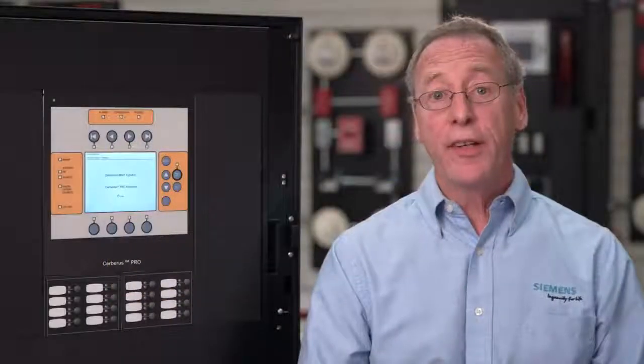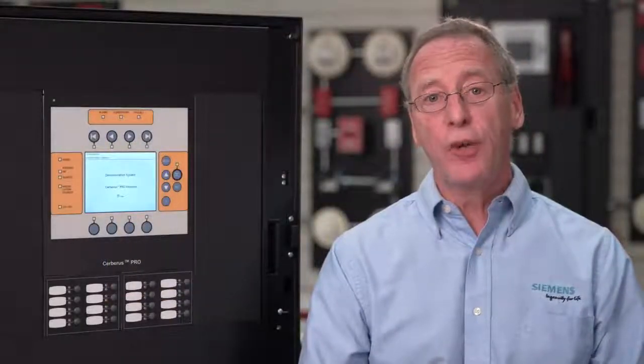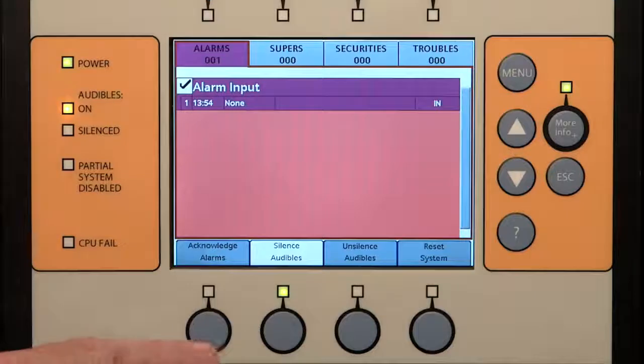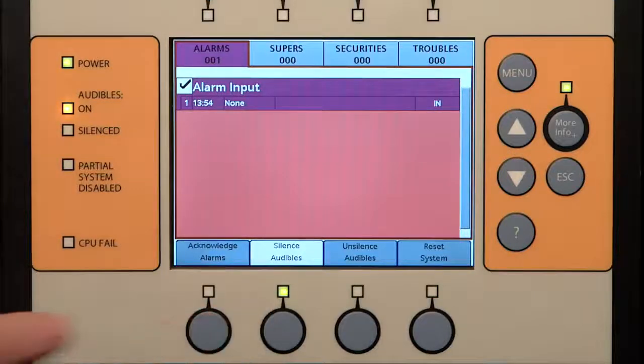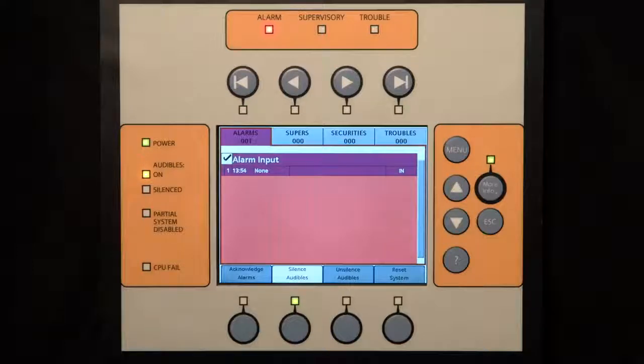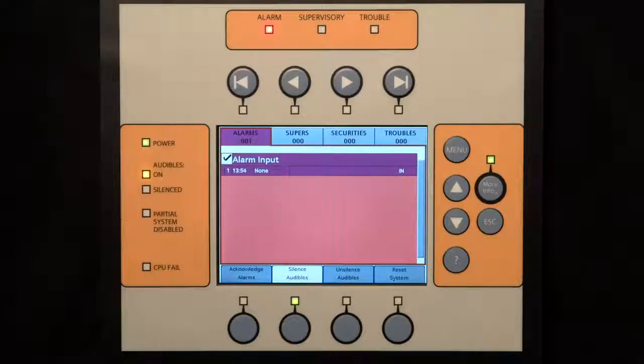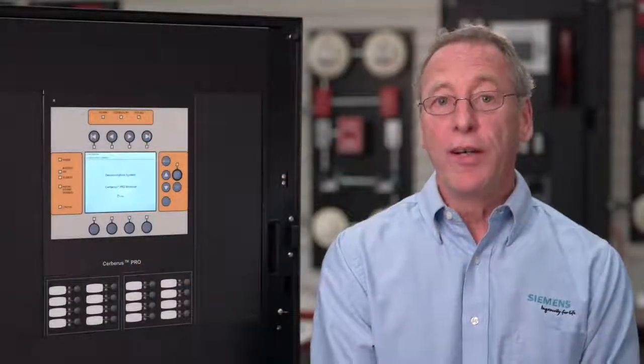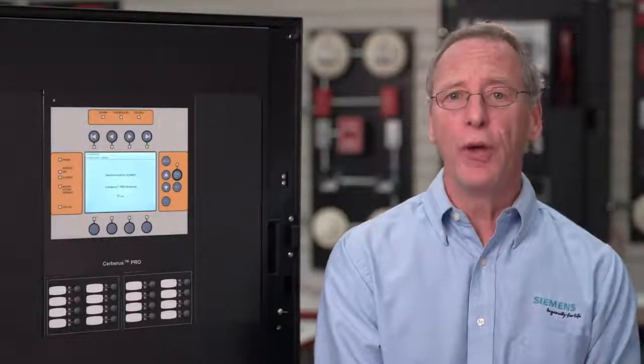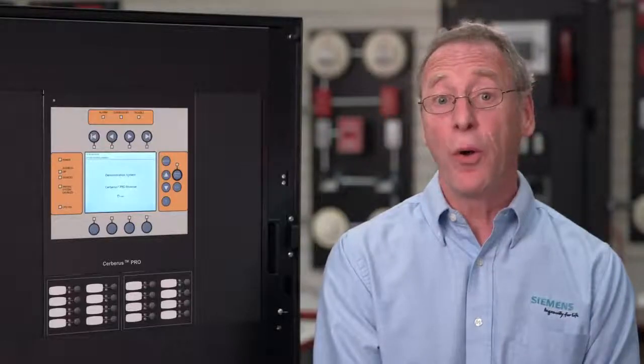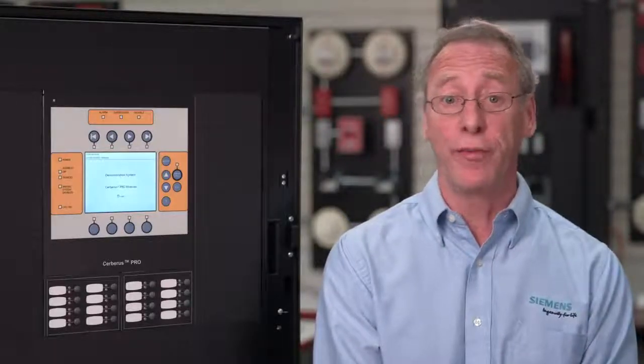Once an event is acknowledged, the next step is to silence the audibles. The silence button is now shown on the display and the LED above the button is lit. When pressed, it will turn off any audibles programmed as silenceable and will light the audible silenced LED. In full operation mode, silencing audibles is only done when authorized, as the building occupants will not notice when the audibles are shut off.